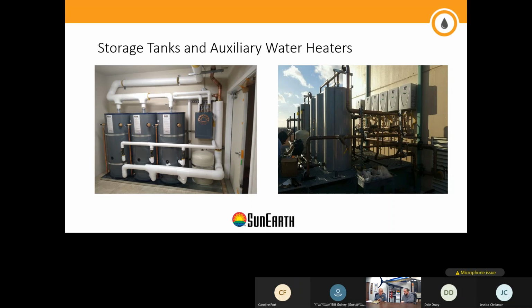Usually, again, in new construction, all this is covered in plan check and plan review. Usually those are caught, yeah, correct. But one thing I realize is a lot of the time, especially on retrofit projects, people are not paying attention to the placement of the equipment they're using. A lot of indoor pumps are being used outdoors, and that always gets called by the inspector. They don't like seeing that because obviously that pump was not constructed to be exposed to the elements over time, and it will create problems. So there are rated and approved solutions that can be used to house that piping outdoors.